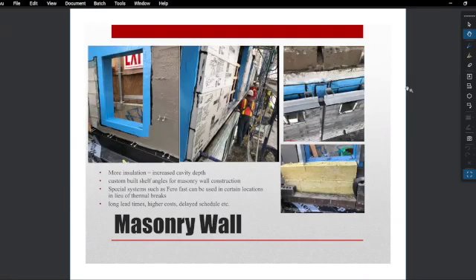These are some photos you see. Top left was a QA/QC mock-up we did with the contractor and the consultants on the job for Metcalf, just to work out the sequencing and the insulation and proper installation requirements as per manufacturer specs. So we would do every step, have the manufacturers come out and verify the thickness, have the consultants come out and verify the placement is correct, and document photos throughout every step to use as a reference throughout construction.